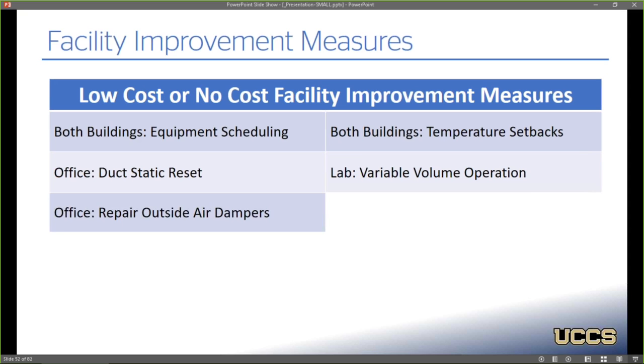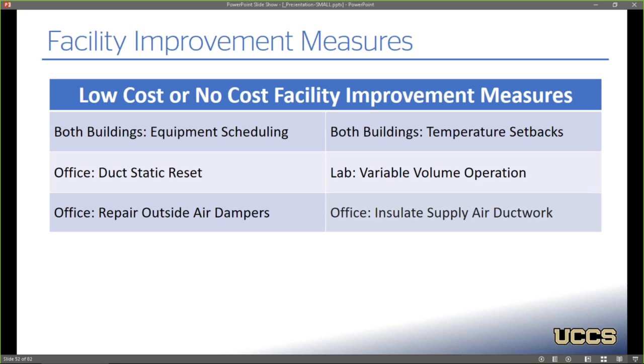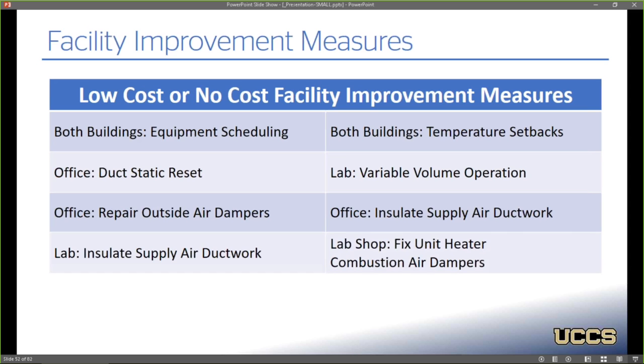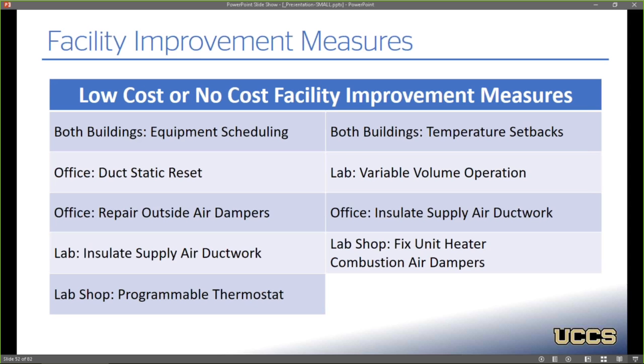At the office, they should be repairing those outside air dampers. They do appear to be leaking quite a bit or stuck in place. So if they can fix them, that can save some energy, that can re-enable economizer operation, and potentially improve the indoor air quality as well. At the office, there's some supply air ductwork that can be insulated, and they should probably do a deeper dive into other areas of the building to see if there are any other sections like that. As well as the lab, they can insulate all that supply air ductwork above the shop. They should be fixing those unit heater combustion air dampers. And that lab shop, they really should install a programmable thermostat, because right now it's a single set point thermostat, doesn't even have capability of programming, and they're just maintaining 67 degrees all the time.